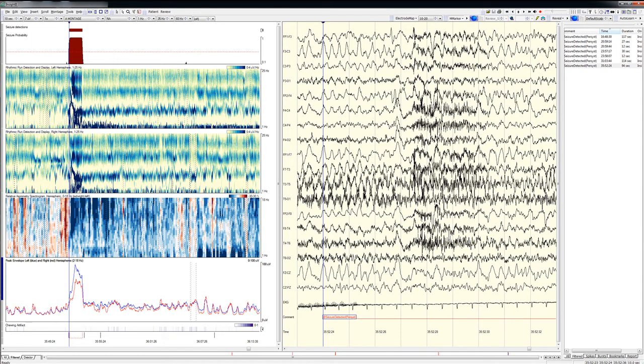Unlike previous generation detectors that usually marked only one detection point, the neural network usually marks much of the full extent of a seizure, as shown in this example. Here, the arrows show the start and stop of a seizure as determined by visual review of the EEG. The Persyst detector's marking closely matches the seizure's extent.